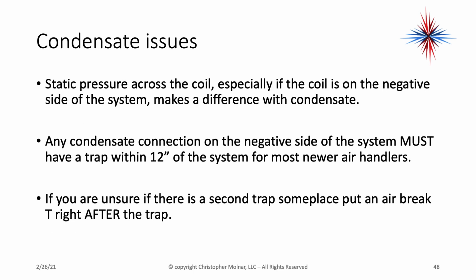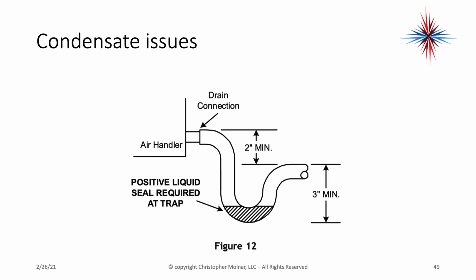Now, static pressures across the coil, especially if the coil's on the negative side of the system, can cause condensate issues. Any condensate connection on the negative side of the system must have a trap within 12 inches of the system for most newer air handlers. If you're unsure if there's a second trap, someplace like under a foundation or possibly a sagging line someplace, put an air break T right after the trap.